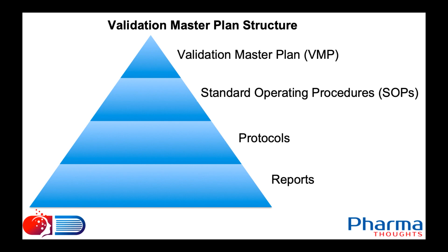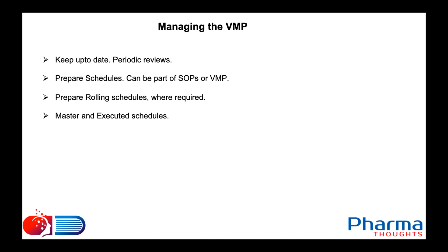These schedules may also be part of SOPs. Examples: preventive maintenance schedule, calibration schedules, area qualification schedules, etc. And one of the best controls is to prepare rolling schedules. For example, if a particular activity has to occur once in 3 years or 5 years, then every year a rolling schedule shall be prepared covering the next 5 years. This will help us not to lose track of activities. And an independent periodic review of executed schedules against a master schedule shall be performed. This will help in better control of activities planned. By ensuring that all the activities are being carried out as planned, we can assure that the systems are being maintained in a validated state.